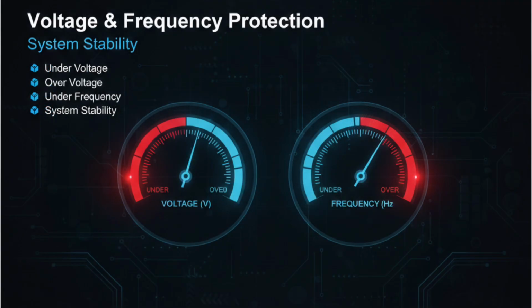Voltage and frequency protection. Voltage and frequency stability are essential for power quality. Under voltage may indicate overload or excitation failure. Over voltage can damage insulation and connected equipment. Under frequency occurs when the engine speed drops due to overload. Over frequency happens during sudden load rejection. Relays monitor voltage and frequency continuously. Minor deviations trigger alarms, major deviations cause trips. These protections maintain system stability and protect sensitive equipment on board.